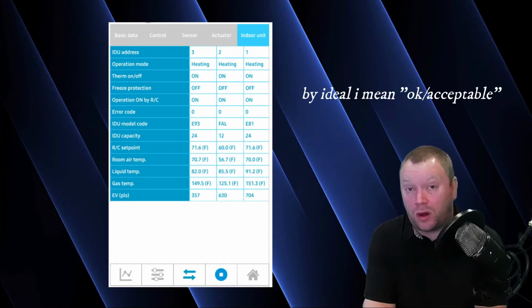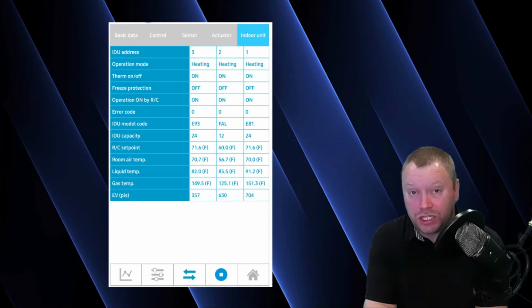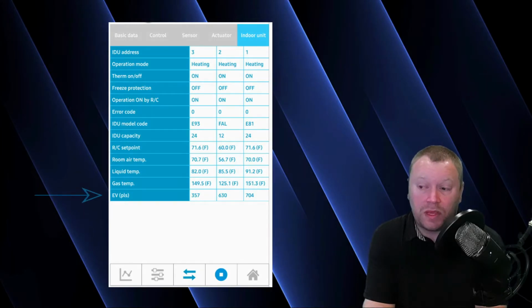Now, this number is always changing because your electronic expansion valve position is always changing to try to control the amount of subcooling which is occurring at the indoor unit. So if we look at the expansion valve here, we can see that we have unit number 3's expansion valve at 357 pulses.